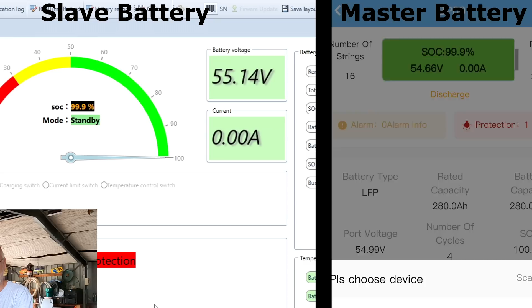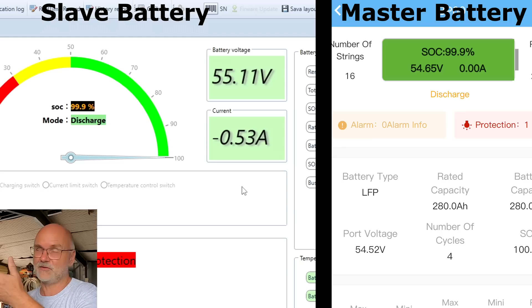We have now reached 55.2 volts in the slave, and we will see the solar charge controller turn off again, starting another microcycle, while the master BMS has again turned off Bluetooth. But we can see it's still at 54.66 volts, so it hasn't moved at all. Now the load is discharging the slave battery again instead of the solar charge controller, using the existing solar energy to do that.